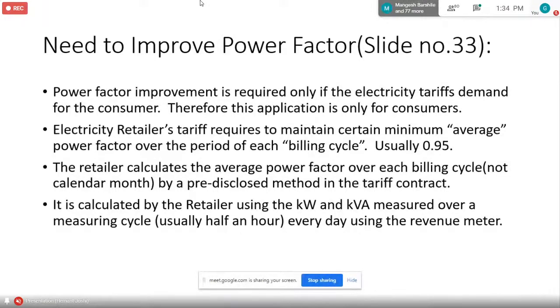Now there was a time a lot of countries didn't have this requirement. For example, New Zealand didn't have this requirement until 1995. You'll be surprised. Now, I don't think there is a country in the world which doesn't have this requirement that a consumer must maintain a power factor above 0.95. Electricity retailer's tariff requires maintaining a certain minimum average power factor over the period of each billing cycle, which is usually 0.95. Remember, billing cycle is not necessarily the month; it is the cycle when the consumer is billed. It may not be the first of the month to the 31st of the month. It depends on the retailer. The retailer may start from the 5th of that month to the 4th of next month or something like that.